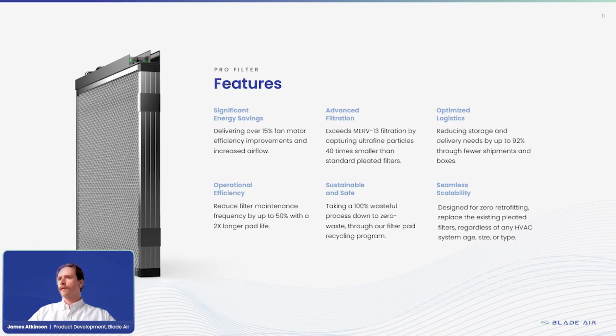So these filters, because they're electromagnetic, have very high performance on the ultrafine particles, right? These are especially effective in terms of wildfire smoke because it's those carbon microparticles. They are attracted to electrostatic fields. They get trapped. We also have VOC reduction. We have some demonstrated third-party testing that shows that we're actually able to trap VOCs as well. And this is because of electrostatic force, right? Normally gas phase pollutants can't be trapped by a filter. But again, we have an electromagnetic force that is pulling these compounds, at a molecular level, into the filter so they can be trapped instead of just by purely mechanical means.